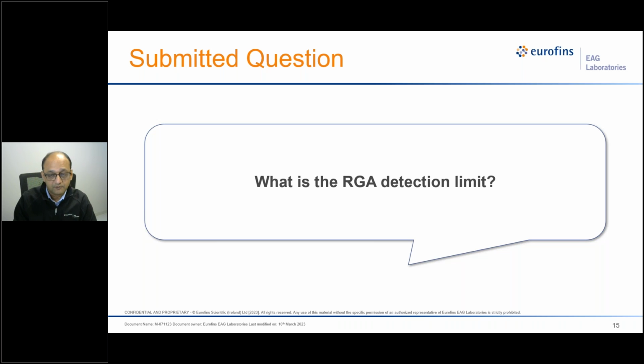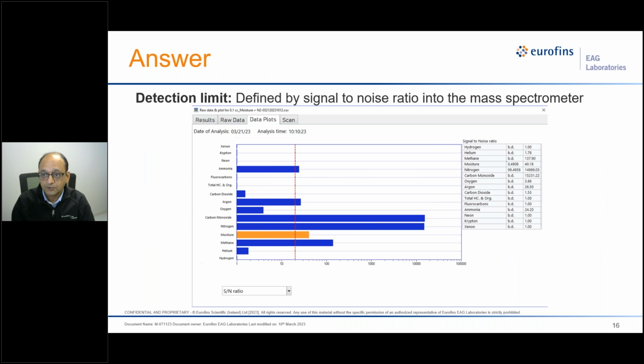Yes, we get this question a lot from our clients, and I think this is a good time to address that. So the first thing is that the RGA detection limit is controlled through the signal to noise ratio into the mass spec. Now, what is signal to noise ratio? As you have seen, we have taken 5 background scans, and then we are introducing the gas into the system. So those 5 background scans give me the background signal strength in the mass spectrometer system, and ideally the signal from the sample gas should be above that background, or let's say noise, in the mass spec system. So the signal to noise ratio has to be positive, it has to be higher than 1.